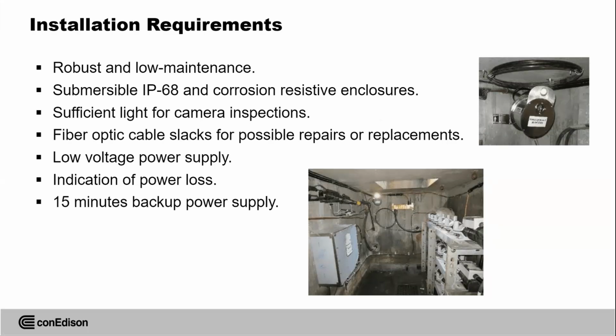So what are the installation requirements? It should be robust and low maintenance. Submersible IP68, then we changed it to IP69, then we changed it to NEMA 4. Now we have NEMA 4 plus 15 feet of water column, 48 hours test. We do the test before we install that system, because we found out with all these hurricanes, rain, and other weather events, some of our manholes, not all, but some of them, get flooded. By the way, we have approximately around 2,000 transmission manholes and dozens of thousands of distribution manholes in our system.